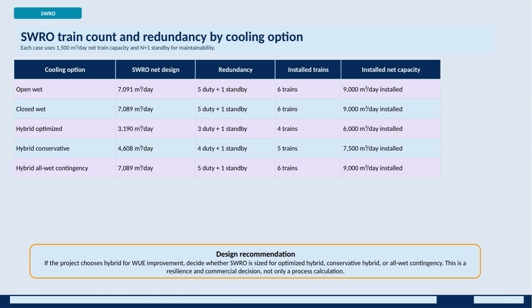The key design recommendation here is that if the project opts for a hybrid cooling approach to improve water use efficiency, it's critical to carefully decide whether to size the SWRO for an optimized hybrid, conservative hybrid, or all-wet contingency scenario. This decision goes beyond process calculations, as it involves resilience considerations and commercial factors to ensure the best fit for the project's goals and risks.